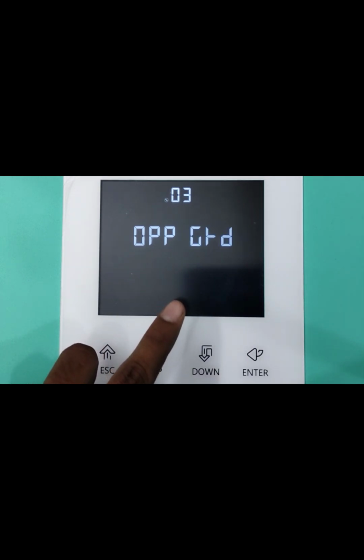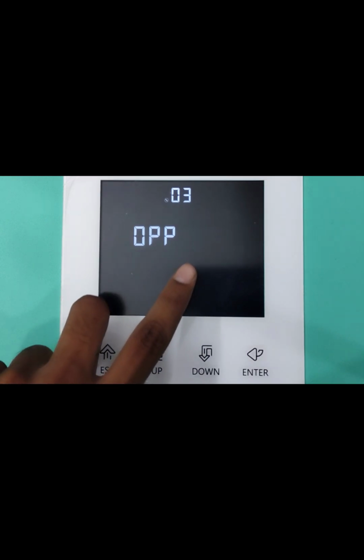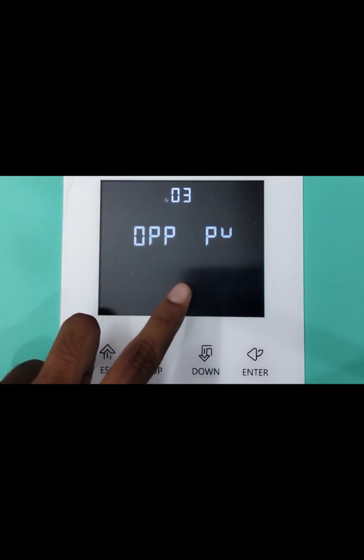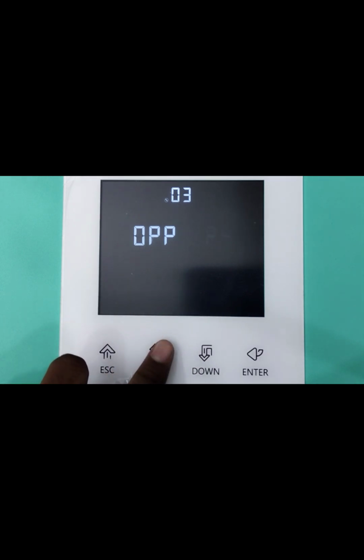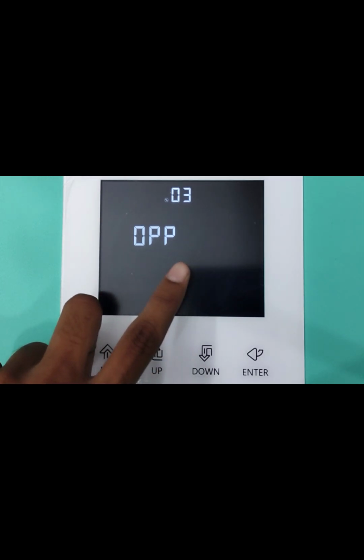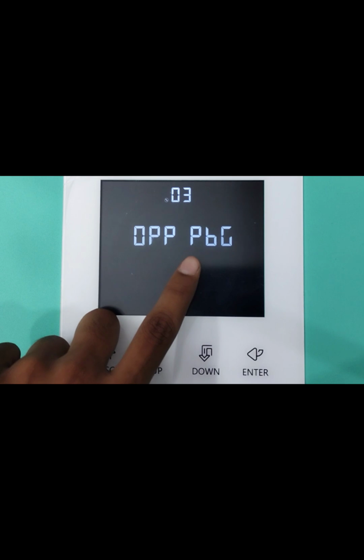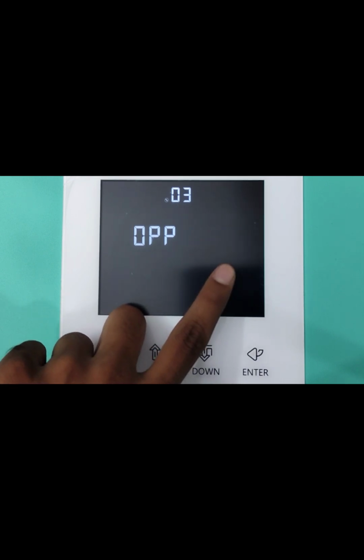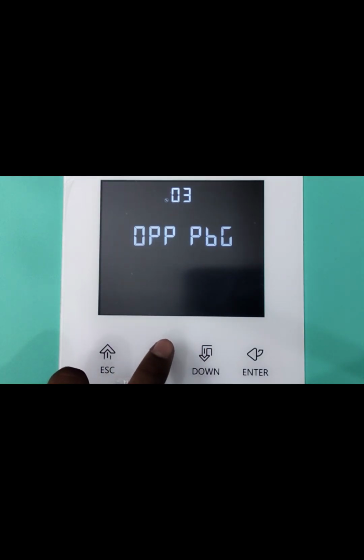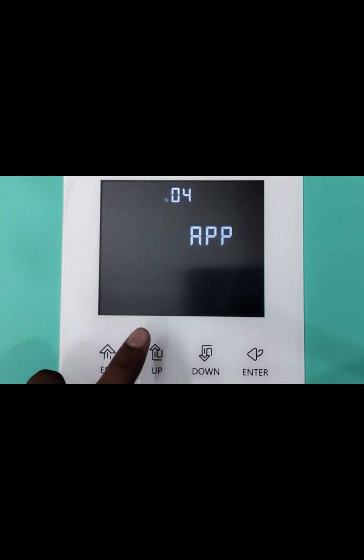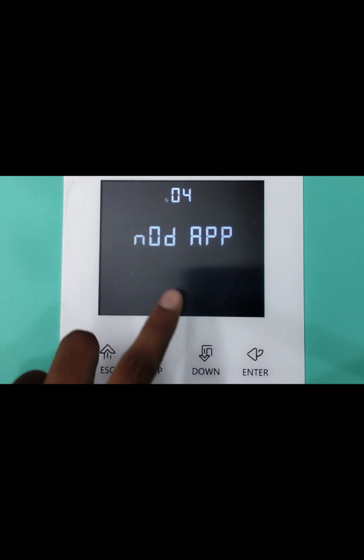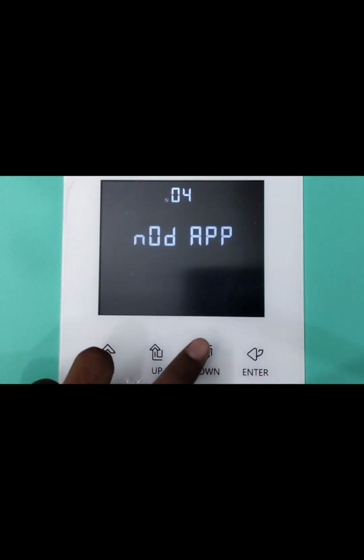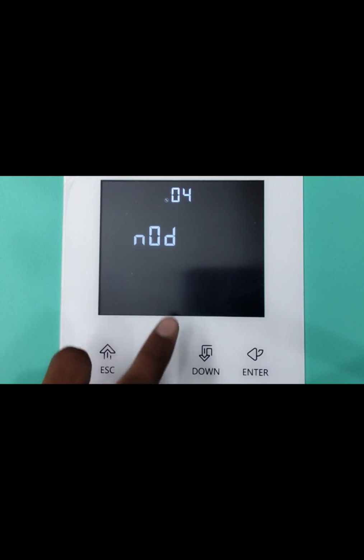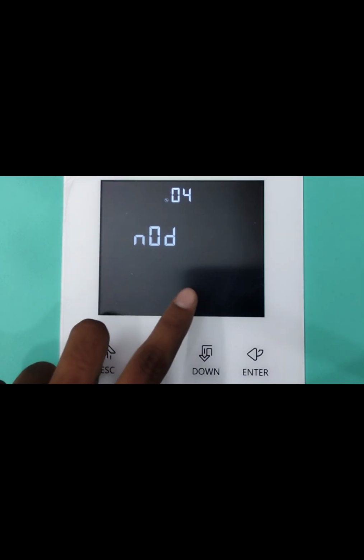Grd means the inverter will give priority to the grid. PU means the inverter will give priority to the photovoltaic. PBG means the inverter will give first priority to PV, then battery, and then grid. Option 4, output mode settings. Here we have 2 options, appliances and UPS.